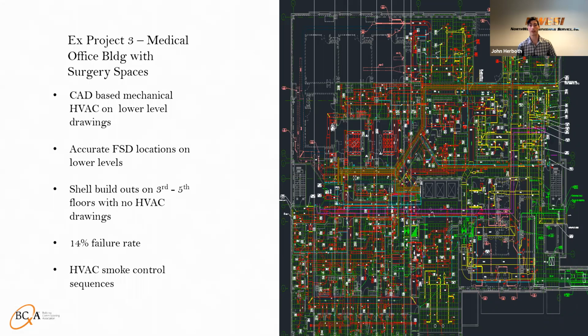These motors fail. They either need to be cycled more often, says the manufacturer, or you cycle them too often and they fail. The problem ends up being the amount of play in the damper assembly, whether at the very end it's torquing down and causing wear on that motor and assembly. These dampers, even new ones rated for 1 million or 500,000 cycles, the motors just fail. It might just be product quality, but this is the whole reason they have to get tested.